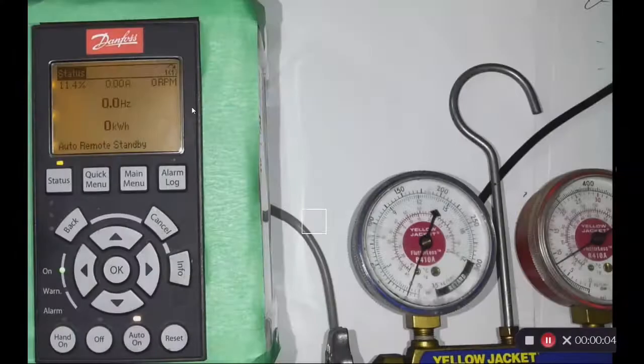does one of his last videos on Danfoss VLT drives. This is going to be part 2 of control of the drive with a pressure transducer. So I have two screens fired up. You can see on the one screen I've got my LCP mounted in my high-tech compartment with the D9 cable, and showing you that we're auto remote and we're on standby mode.